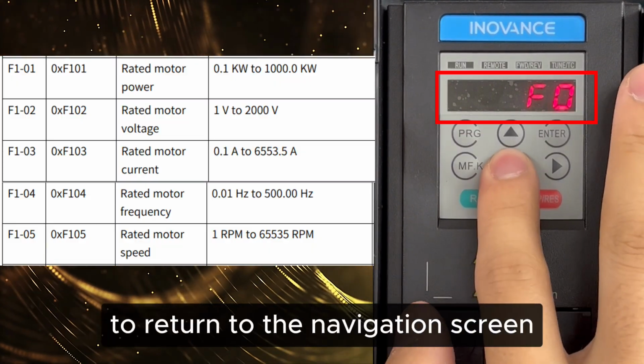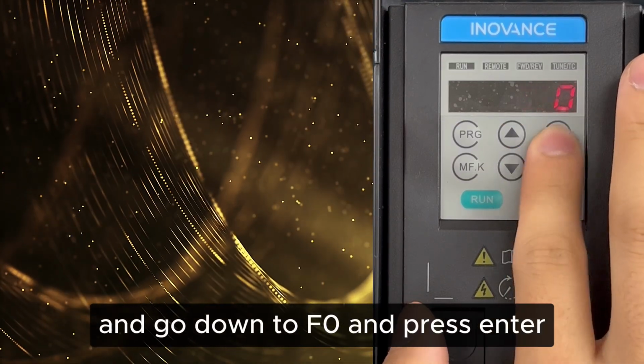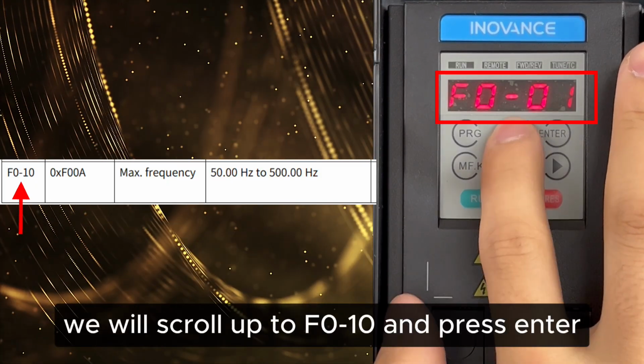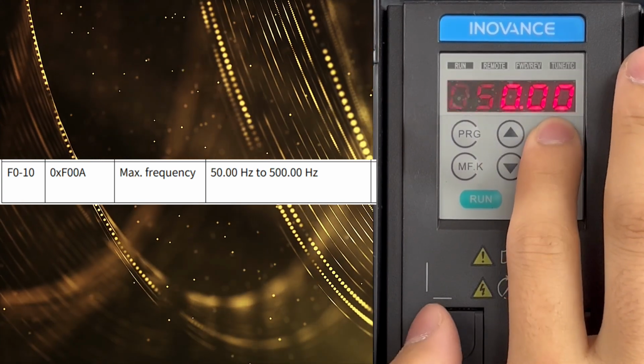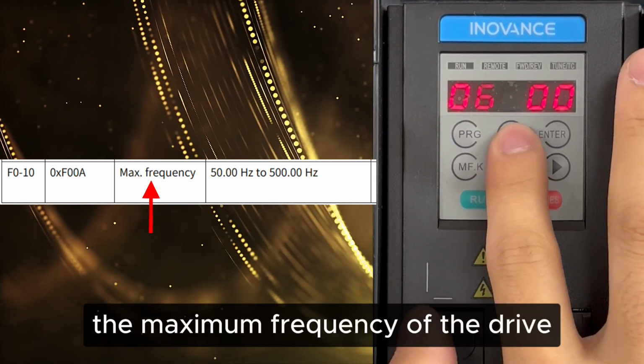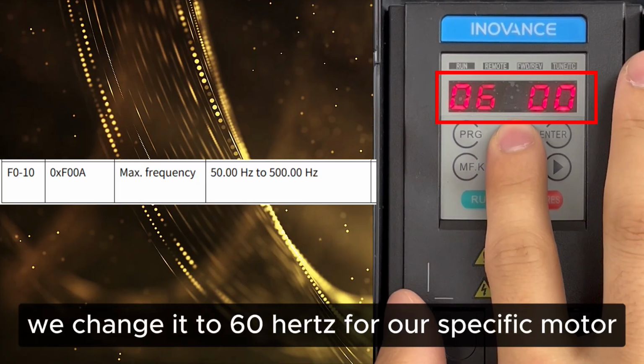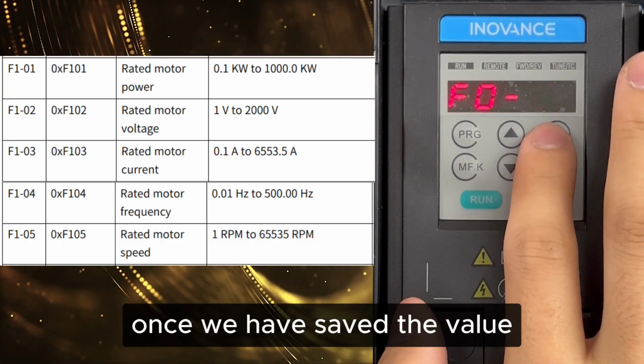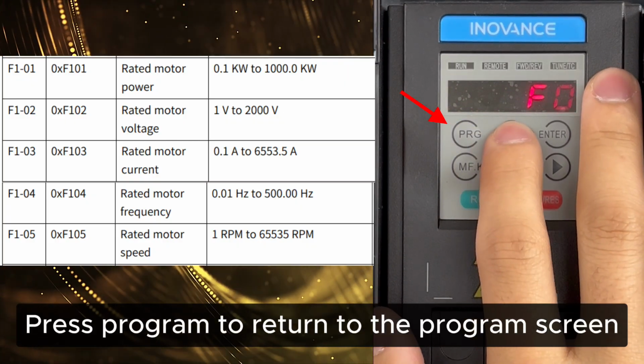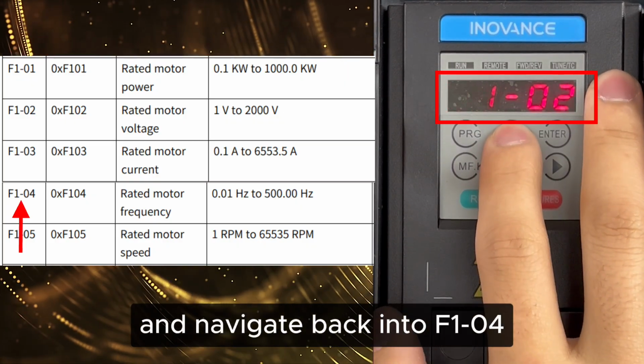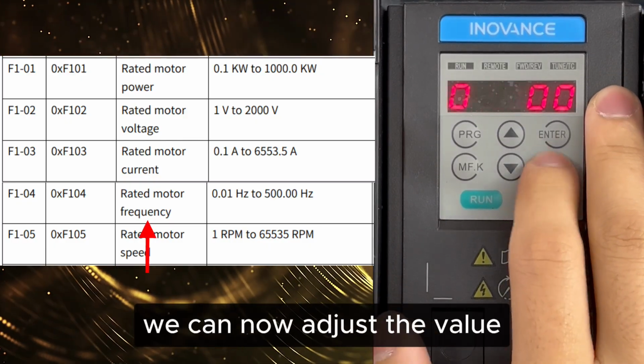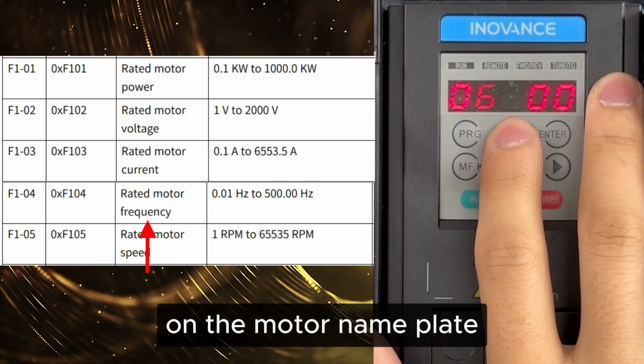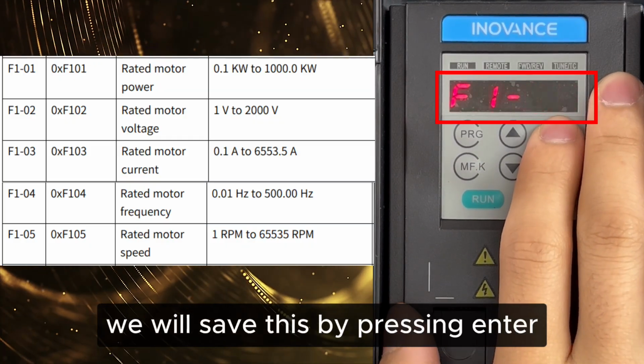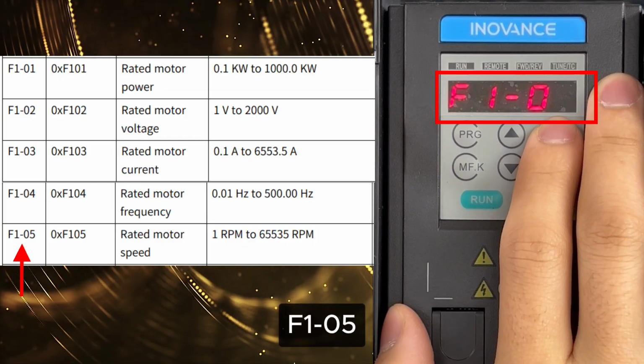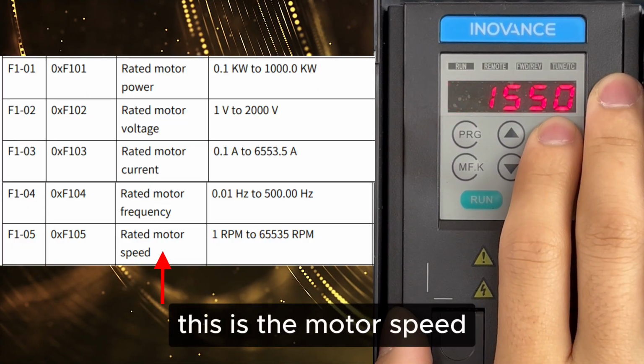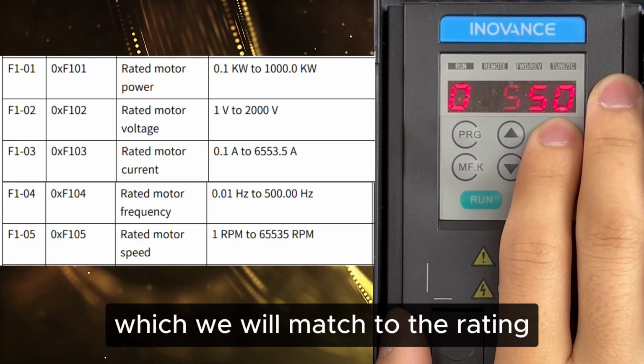Press the Program button to return to the navigation screen and go down to F0 and press Enter. We will scroll up to F0-10 and press Enter. Here we can change the maximum frequency of the drive, which for this example we change to 60 Hz for our specific motor. Once we have saved the value, press Program to return to the program screen and navigate back into F1-04. At this point, we can now adjust the value to match the one listed on the motor nameplate. We will save this by pressing Enter and proceed to change the last parameter, F1-05.